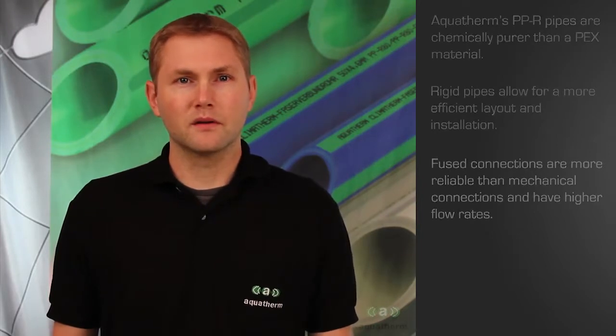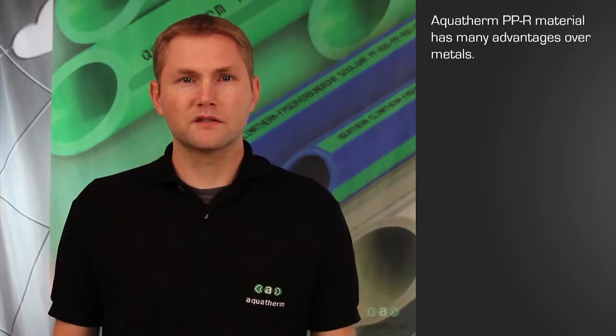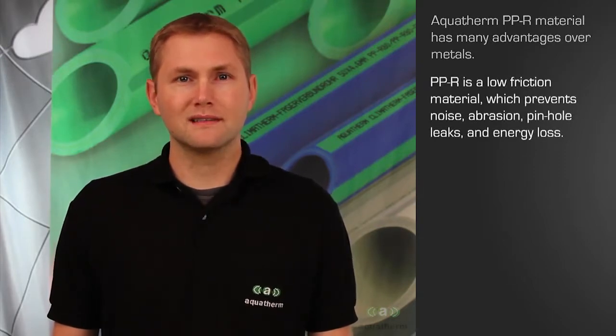Compared to metal piping, there are many advantages as well. Polypropylene is smoother than metal pipe, making the pipes quieter as well as using less pumping energy. There are also no problems with abrasion, which can wear out metal pipe and cause leaks.